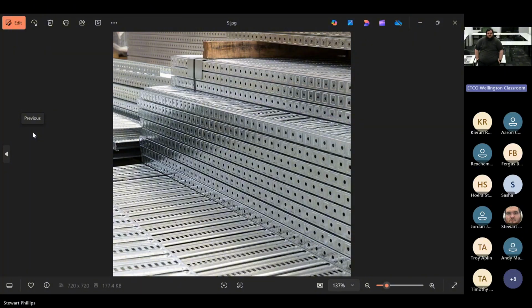And then this is your cable tray. It comes in varying widths. What considerations might we need to worry about when we're installing things like cable ladder and cable tray? Cable burn, earthing, yep. Bonding, the weight of the cables, yep. Brackets, the distance, yep. Generally you don't want more than, I don't know, Andy, how far apart do we run the Unistrut for the hospital? Ventilation, yeah. Heat between the cables being close together, yeah. The magnetic effects. What kind of cables are going to run on the cable tray? Is it going to have both data and power?